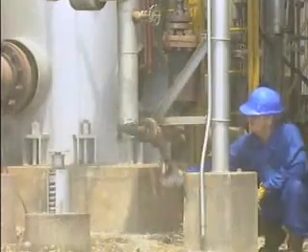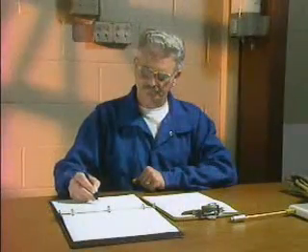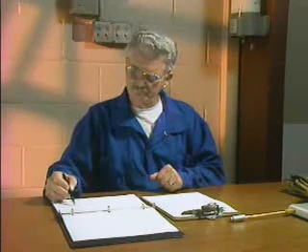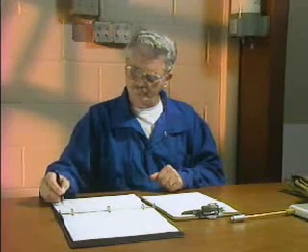Another task that's usually part of a trap station survey is making sure the trap strainer has been blown down. Opening the strainer blow-down valve one full turn and then closing it will usually provide enough flow to clean out the strainer. Finally, you should keep a record of the trap station's performance or operating history, as reviewing this may reveal specific problems to check during a survey or clear up questions about how the trap station has performed under certain operating conditions.